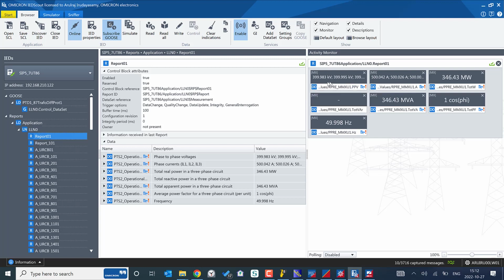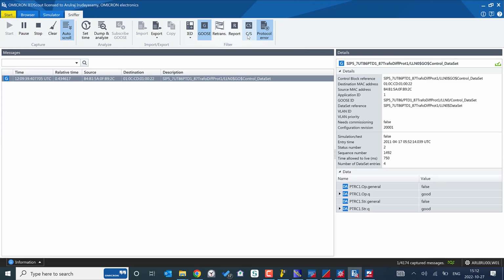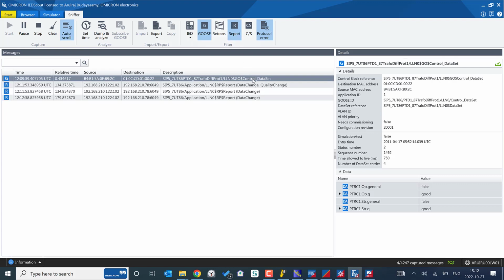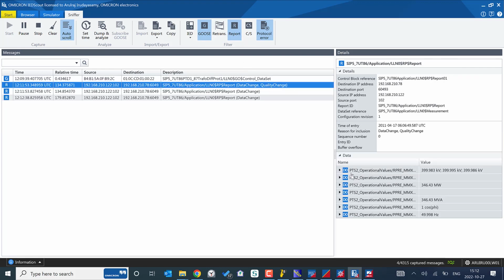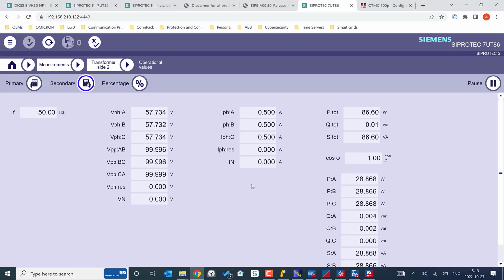So those are the 400 kV, and then we also see the current definition, which is 0.5 in the secondary, 500 ampere, which we can monitor, and the report is also received, and we can get those report information here, which report has been received by IEDs code for the data change that happened. You can also monitor, and also export the information, the test report that you verified all this information.